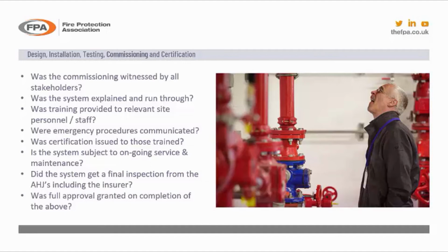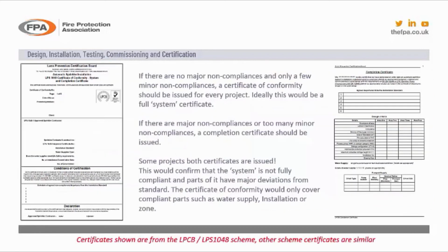Did they find any snags or slight non-compliances maybe that need to be captured and altered just to ensure that it complies, so they're happy that they've got a fully sprinklered building that they can insure, and was full approval granted on completion of all those questions. So these questions are relevant to the commissioning, but the questions that I would suggest are asked of contractors to ensure that these things are done, most of the time they are done, like I say, but just a key stage that will ensure that the system is handed over correctly. When it's handed over, so we've gone through the design, the installation, we've tested it, we've commissioned it, everybody's involved, the contractor must provide certification.